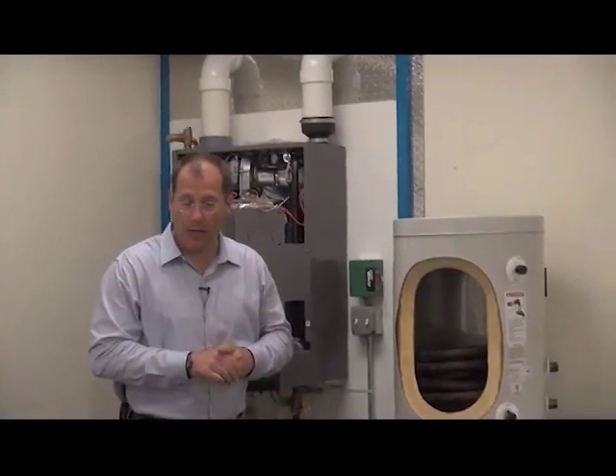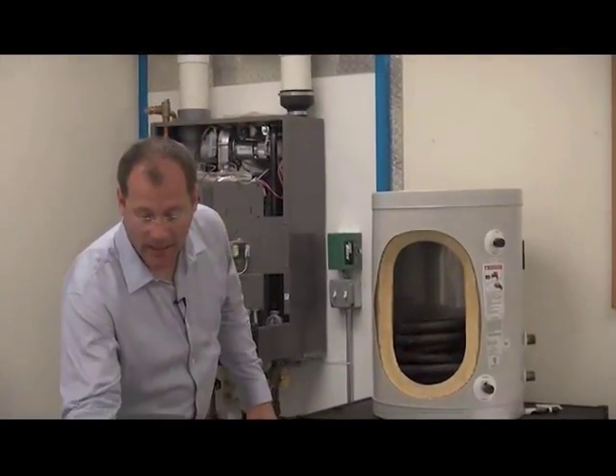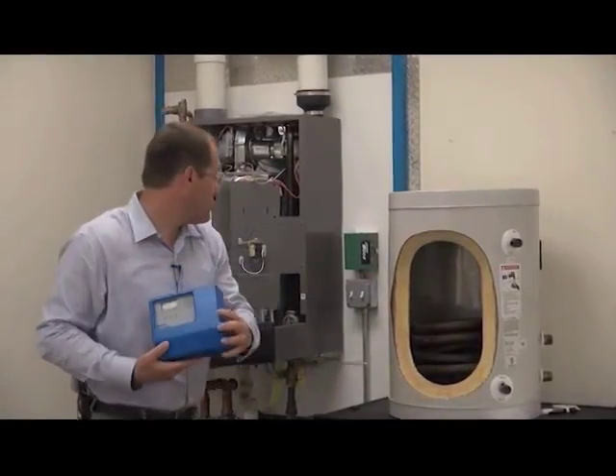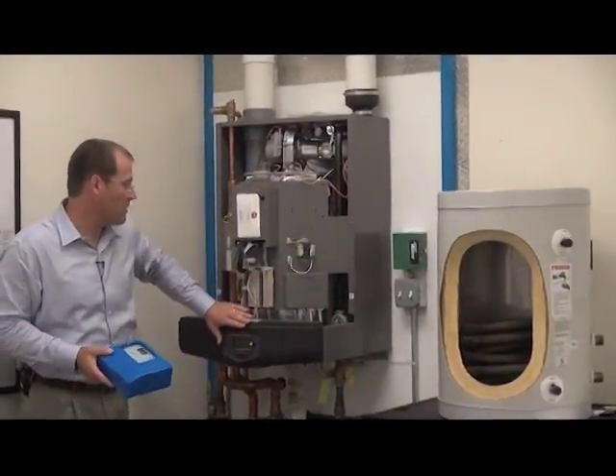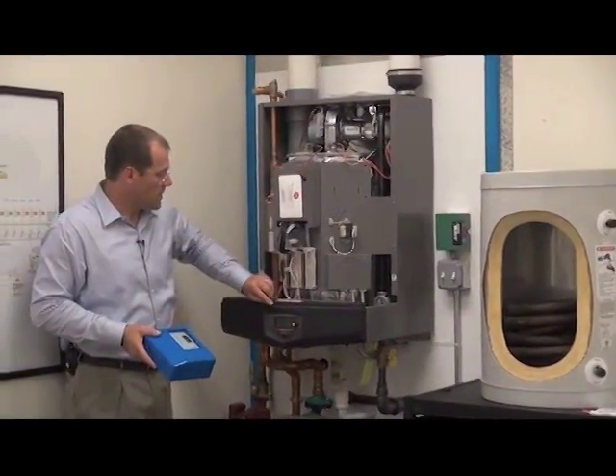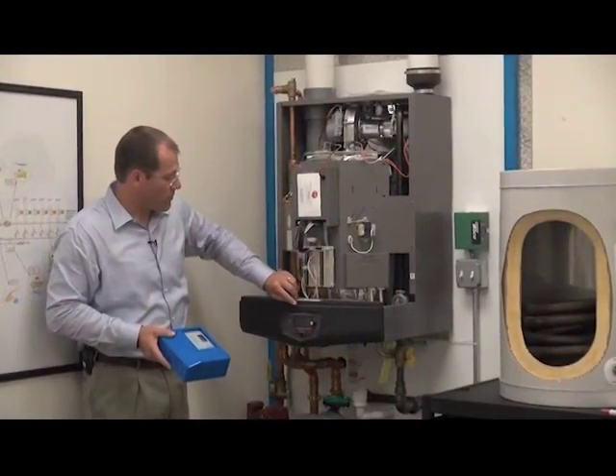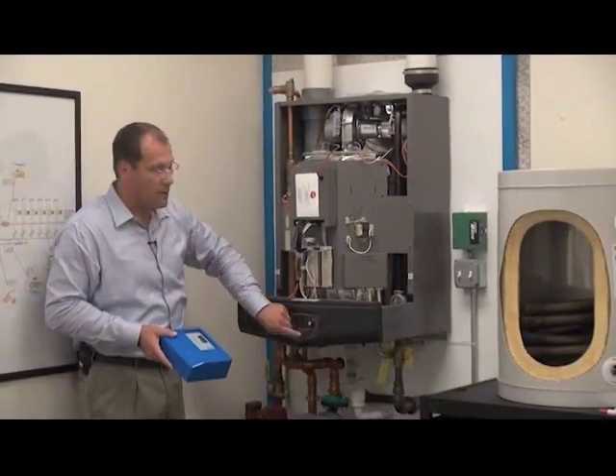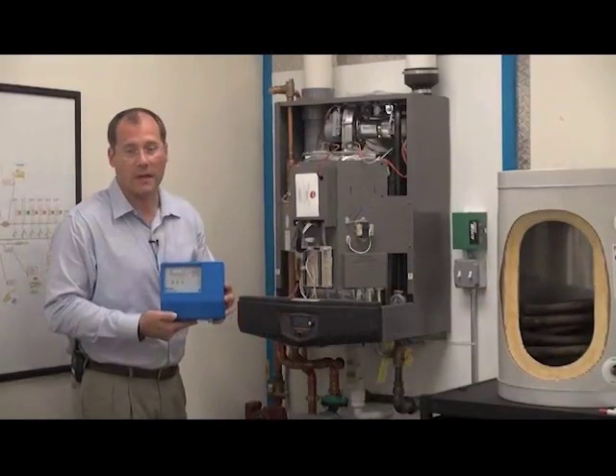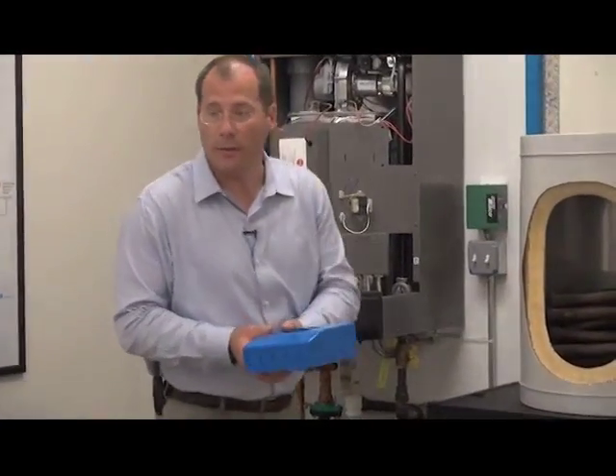Reset control. Yeah, so what we talked about earlier, adding a reset control to an existing piece of equipment, this is now included in the logic of the newer boilers. So all of your new condensing wall-hung boilers or floor-standing boilers will have this smart control that includes the outdoor reset. So that feature is built into all of the new equipment.